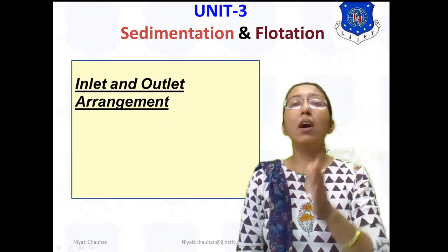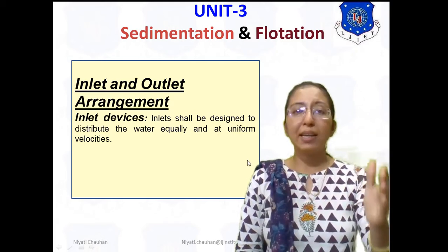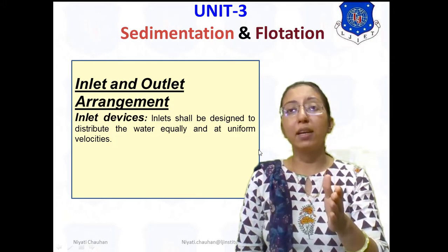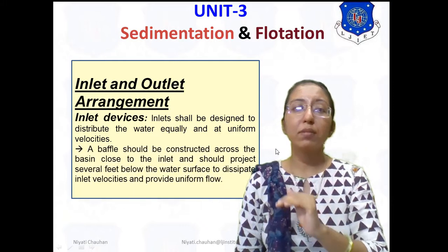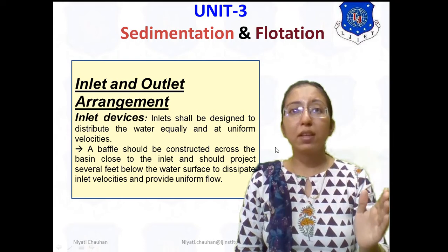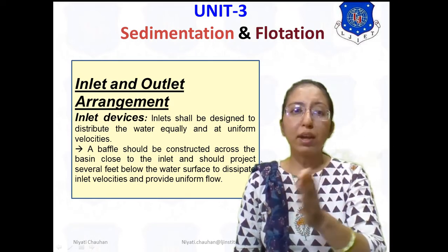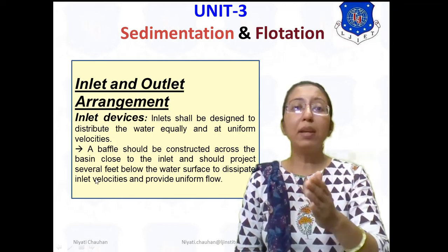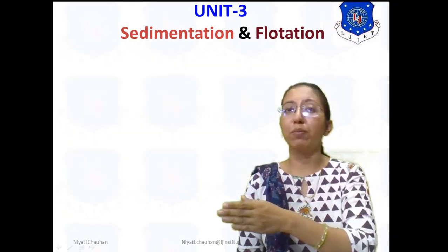Inlet and outlet arrangement. Inlet devices: the inlet shall be designed to distribute the water equally and at uniform velocities. A baffle should be constructed across the basin close to the inlet and should project several feet below the water surface to dissipate inlet velocity and provide uniform flow.